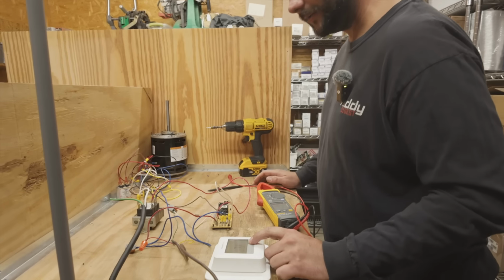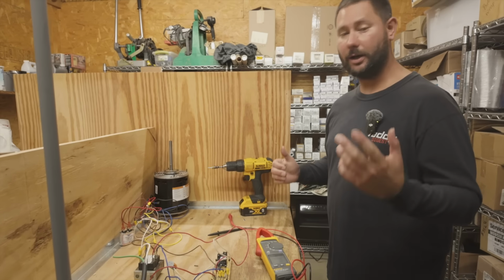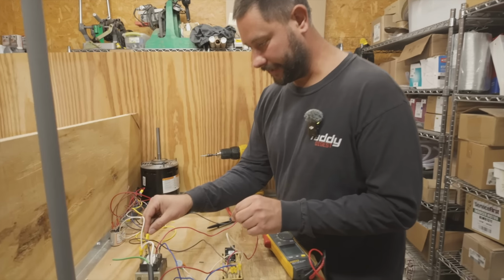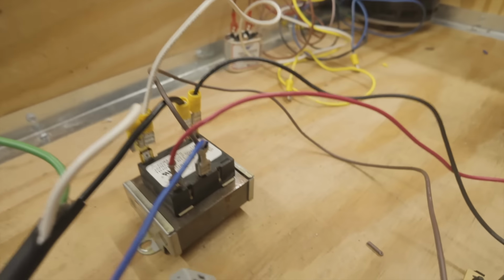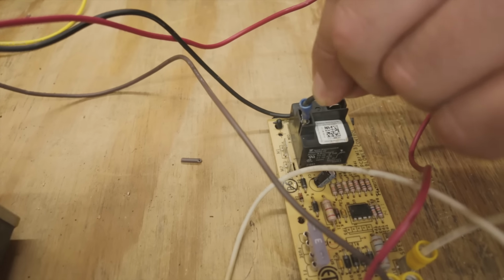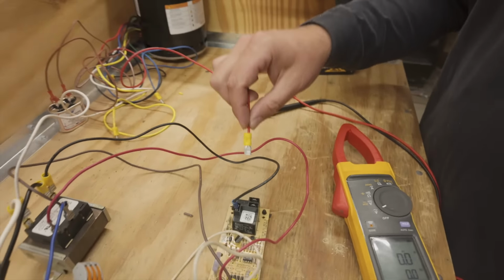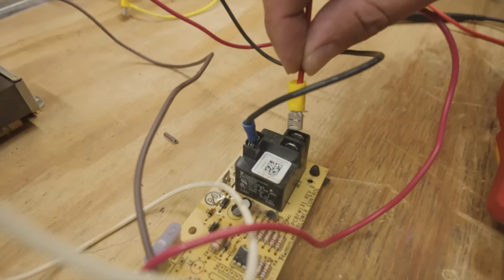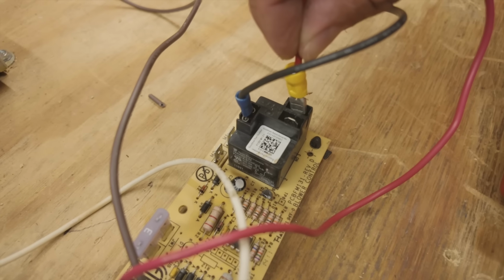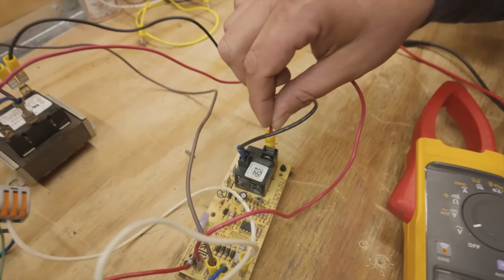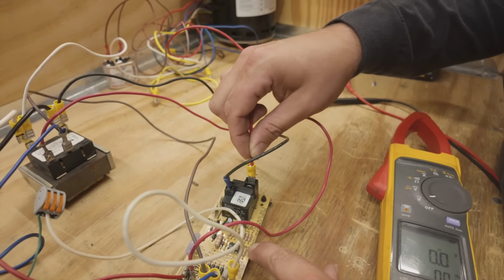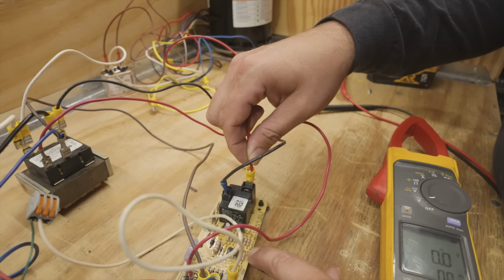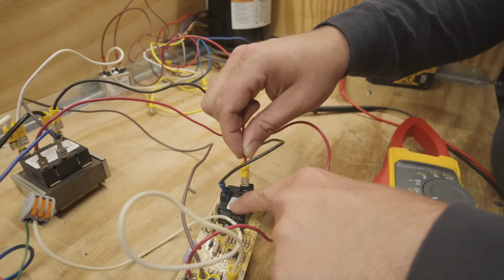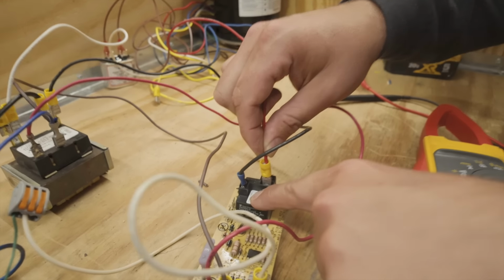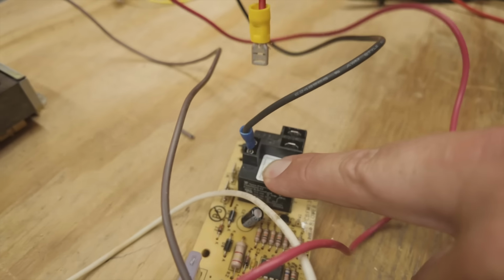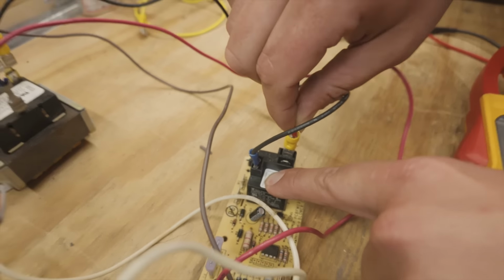All right, so let's go ahead and turn it off. Take the call away. And then let's hook up our fan motor wires. All right, let's bring in that other side of the line from the primary side of the transformer into the relay. And then let's bring in this low speed wire to, if we put it here, it's going to kick on, right? Oh, wait, that was normally open. That's right. So be careful. Oh, looks like we got an issue with this board. See? Normally closed, it runs. Normally open, it will not unless we give it a call.